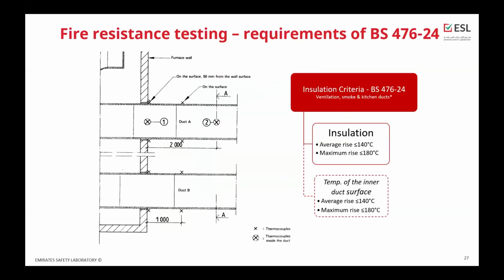So for assessment of the insulation, we are using the temperature measurements on the unexposed side of the duct. BS is describing 8 thermocouples as a minimum, 4 thermocouples, 1 on each side, 50 millimeter away from the wall, and then 1 meter away from the wall. The insulation criteria is either average or maximum.